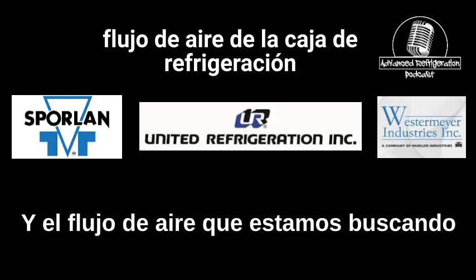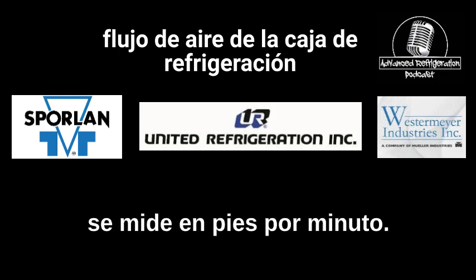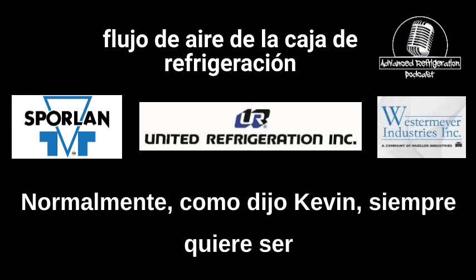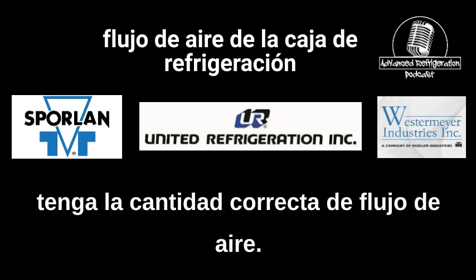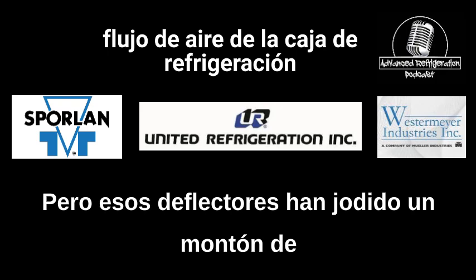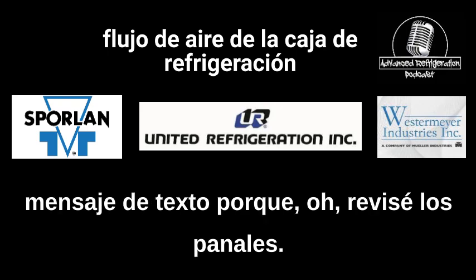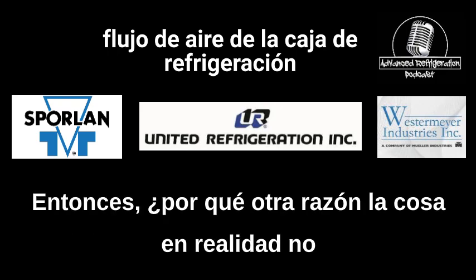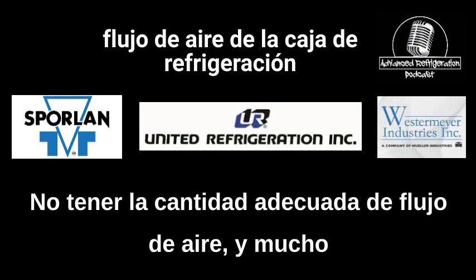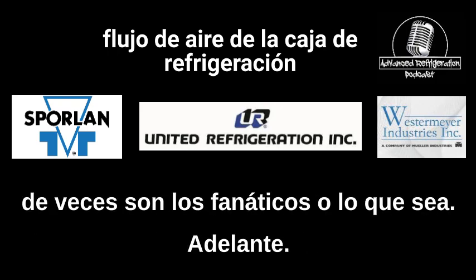And the airflow that we're checking for is measured in feet per minute. Normally, like Kevin said, it always wants to be checked directly after a defrost to make sure you do have the correct amount of airflow. But those baffles have screwed a lot of techs over because I checked the honeycombs, that's fine. I checked the coil, that's fine. So why else wouldn't the thing pull down the temp? Not have the proper amount of airflow? And a lot of times it's the fans or what have you.